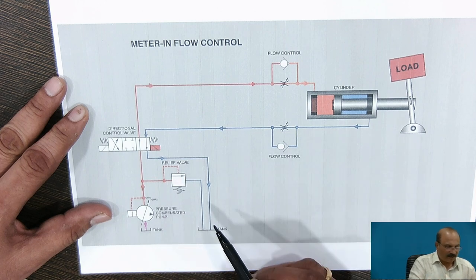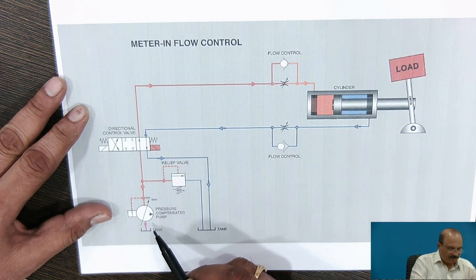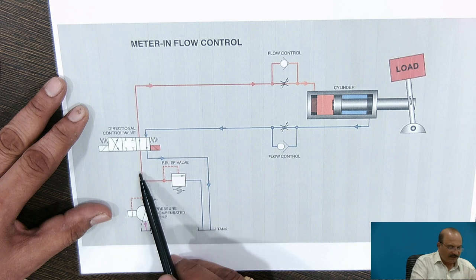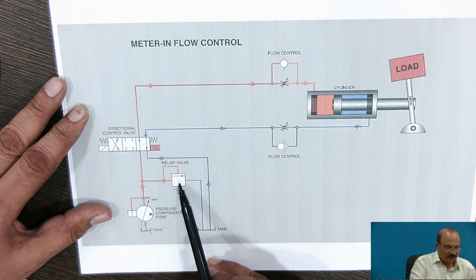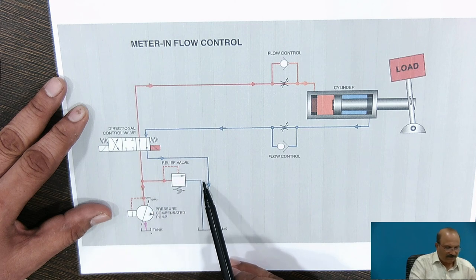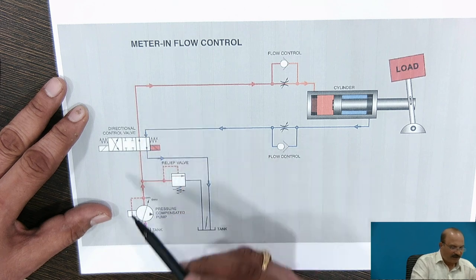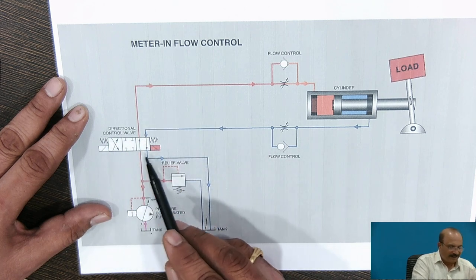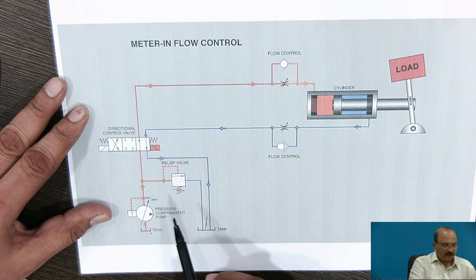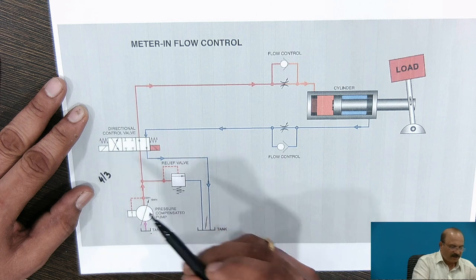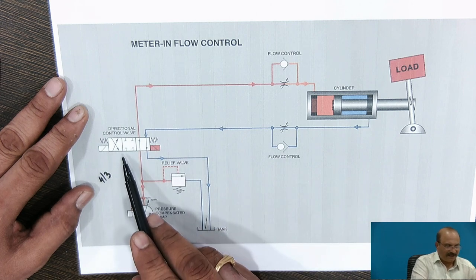So here we have the storage tank, then it comes to the pump. Whatever oil is being pumped in the upward direction, if the pressure is more than the designed pressure, then through the relief valve it will come back to the tank. While going in the upward direction, there is a directional control valve — we are calling this a 4 by 3, meaning 4 ports and 3 controls.